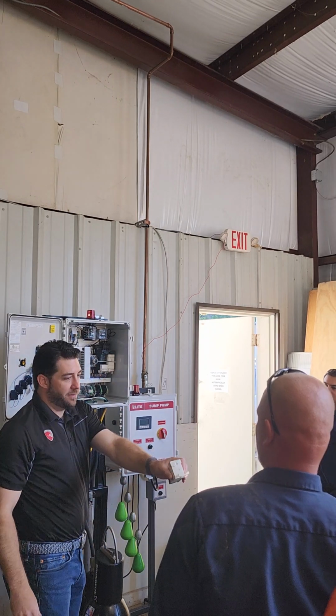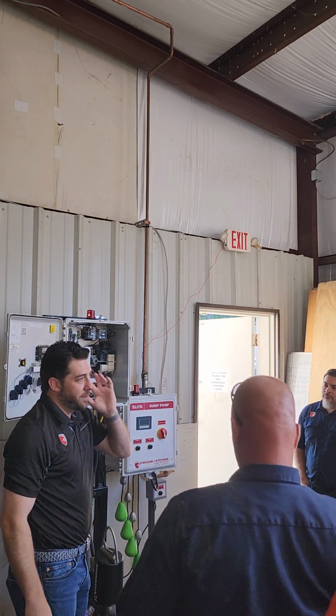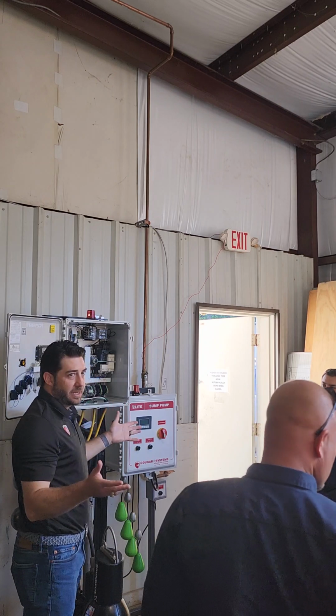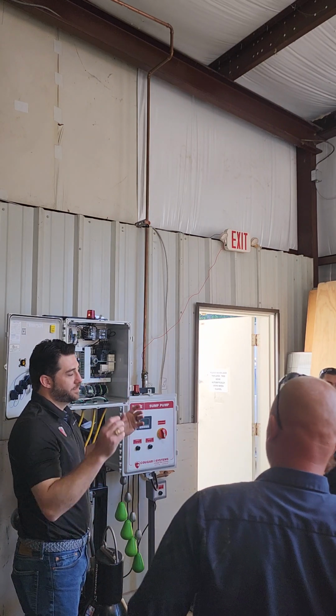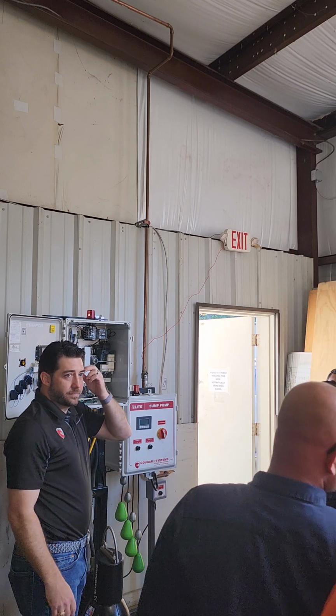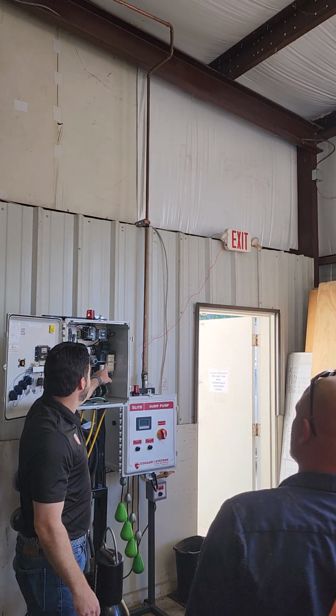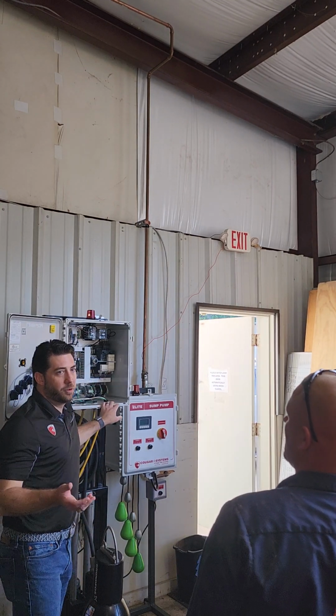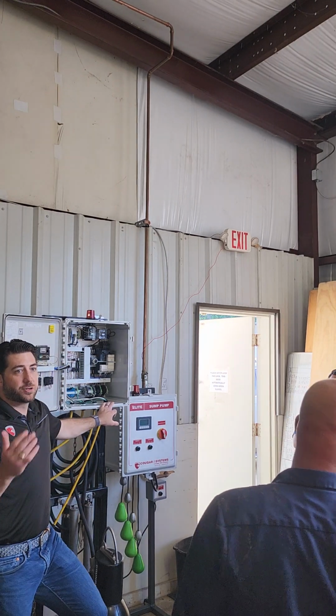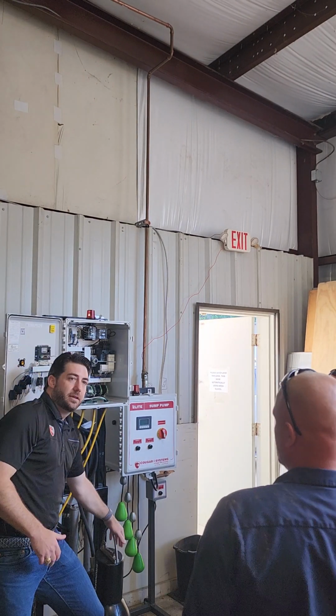And so we can pop out the overload relay, and we can swap it out for a different one. Instead of the inventory having to carry one panel, you don't have to rewire. You're saying overload. What do you mean by overload? So overload protection is for the motor: it trips when the amp draw goes over what the rated nameplate is.